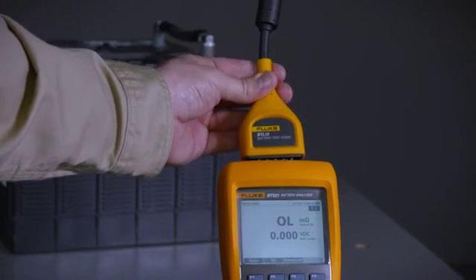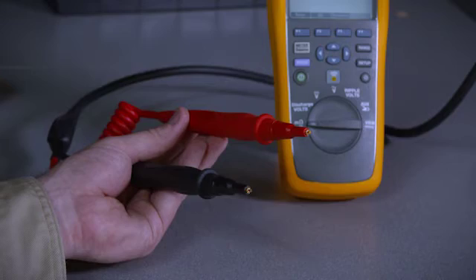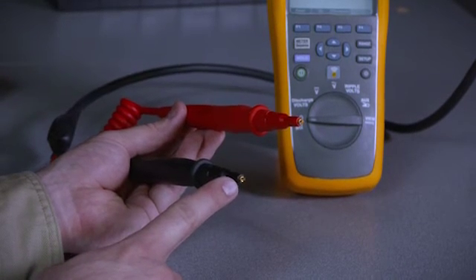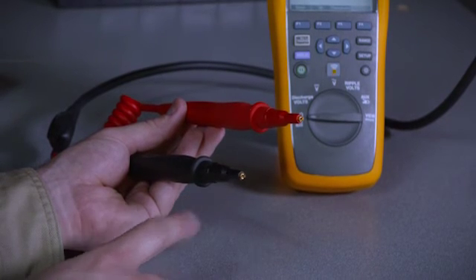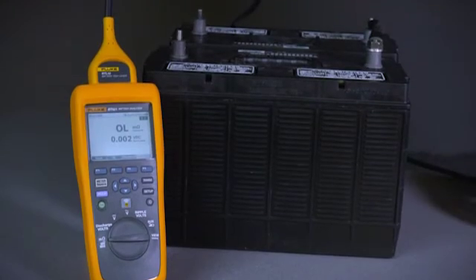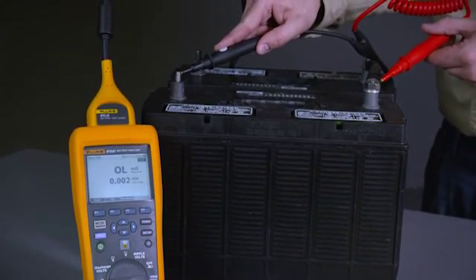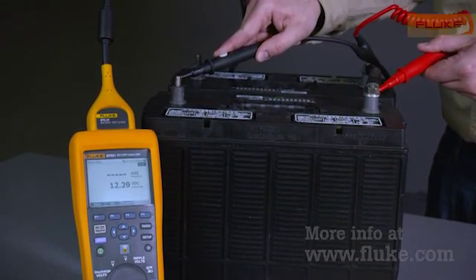This is the BTL 10 probe which is a simple two-prod probe with a Kelvin connection. This insulated center pin carries current while the outer pin measures voltage. Voltage drop caused by the test current draw is zeroed out by the Kelvin connection, nullifying its effects.